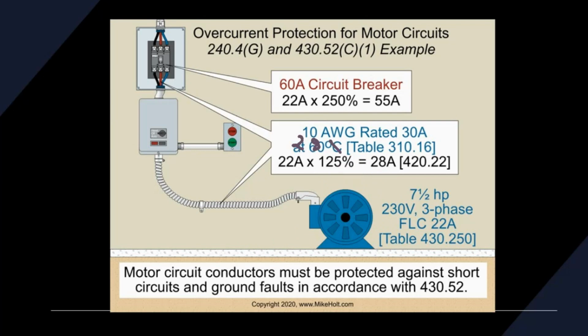All right, so here's another example. In this example, this is a 22 amp. 125% ends up with 28 amps. So at 28 amps, you could use the 60 degrees Celsius table for a number 10 as well, if you're in the 60 degree column. Okay, and I believe, let me double check.